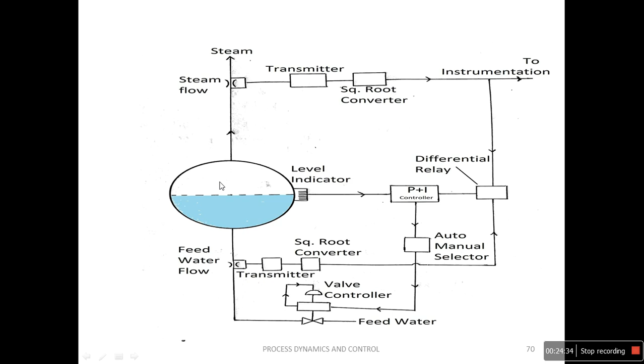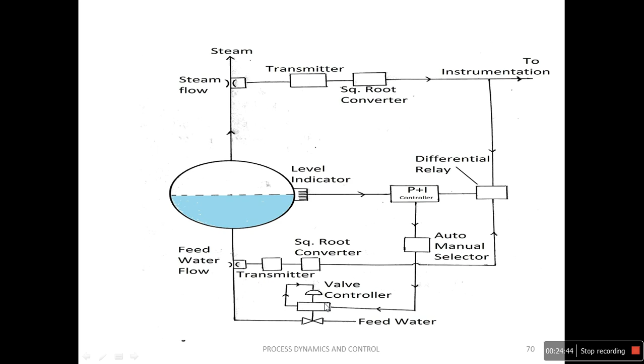This level may be varied either by changing the feed water flow rate or by changing the steam flow rate. As we have already discussed feedback, feed forward and cascade control, we may have to use any one of those. Clear? Here the feed water flow rate can be measured and controlled. Here we will see the different types of controls we are using and the need for drum level control. A dramatic decrease in this level may uncover the boiler tubes, allowing them to become overheated and damaged.